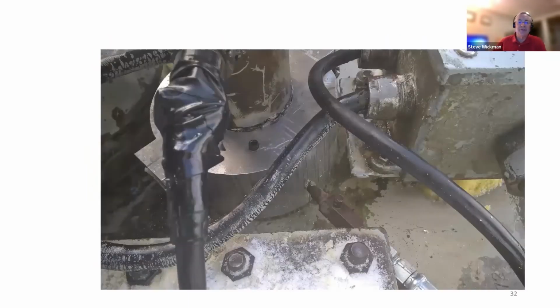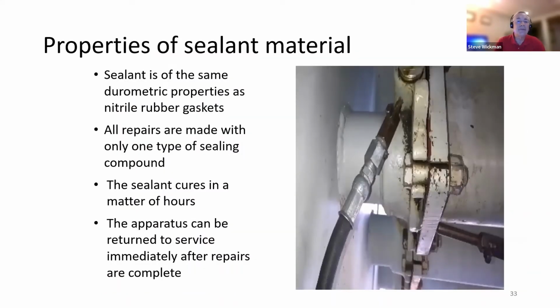And in this one here, you can see the injector valve, and you can see one of those pipe plugs that's been partially screwed into one of the holes on this clamp where the sealant's gone in. And you can see the injector in place, pumping the sealant into the side cavity right here. The sealant material is of the same durometric properties as nitrile rubber gaskets, as I kind of mentioned earlier. This repair technique uses only one type of sealing compound, as opposed to high pressure industrial leak sealing, which may have different sealant compounds depending on the temperature and pressure and material that may be flowing inside the piping that's being addressed. So the technicians doing this low pressure seal technique in substation facilities don't have to be chemists. They don't have to determine what the right stuff is to use. There's only one type. Cures in a matter of hours, and the apparatus can be returned to service immediately after repairs.